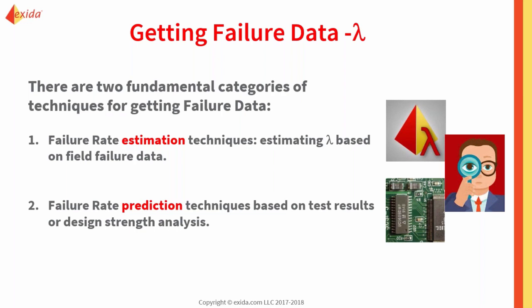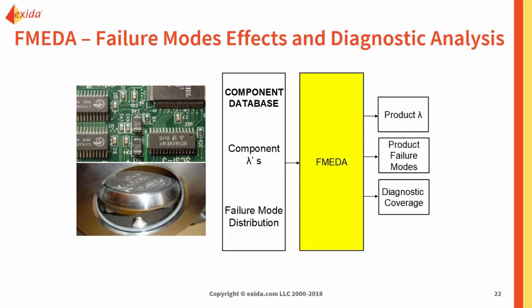That is predicting a failure rate based on either test results or design stress strength analysis. For low demand mode of operation, we generally talk about FMEDAs. For high demand, we can talk about FMEDAs or more test-based results. But for this webinar, I'm going to concentrate on process industry and low demand, so I'm going to only talk about FMEDA and the design stress strength analysis of failure mode effect and diagnostic analysis, FMEDA.